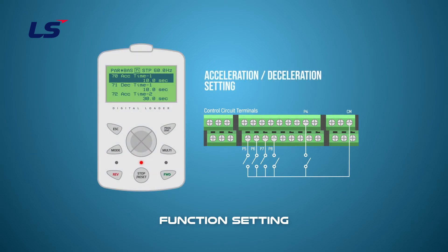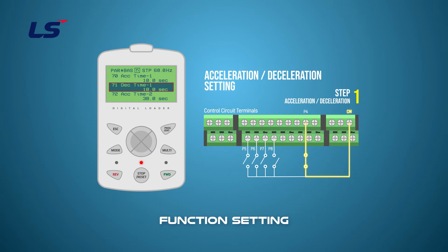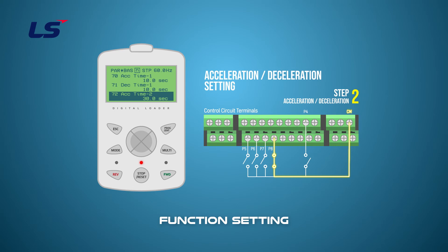Terminal P4, which is XCEL-L, stands for step 1, and sets the multi-stage acceleration-deceleration to BAS70, accelerate time 1, and BAS71, decelerate time 1. Terminal P8, which is XCEL-M, stands for step 2, and multi-step acceleration-deceleration for step 2 is set to BAS72, accelerate time 2, and BAS73, decelerate time 2. If terminals P4 and P8 are entered at the same time, it is set to multi-step 3 and reflects the acceleration and deceleration times set at BAS74, accelerate time 3, and BAS75, decelerate time 3.